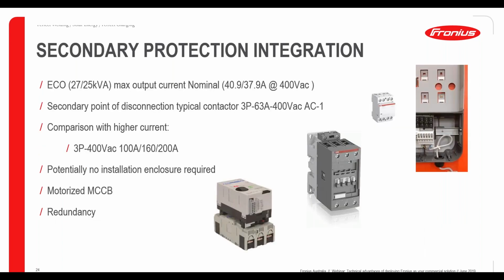We see there are three typical pictures. If we start from the left and go all the way across, we'll see a small typical 63 amp contactor, looking like something on the right. As the contactor size rises, we get something bigger in the middle here, and then a motorized circuit breaker is basically a breaker with the add-on shown in the picture here. Why this matters is that with the ECOs, we have increased flexibility for that disconnection point. Typically, if the contactor size is smaller, we have a small area inside the ECOs that can potentially be used for disconnection. Obviously, it depends on site and size as well. But that is shown in the picture on the far right here. There's a small DIN rail that can be used for that typical 63 amp contactor.